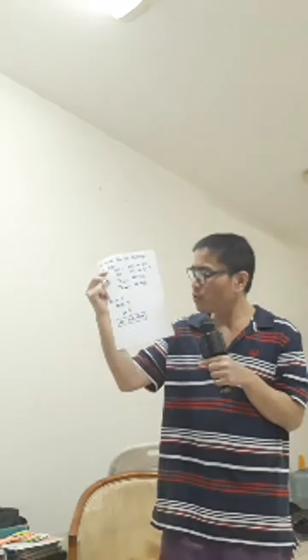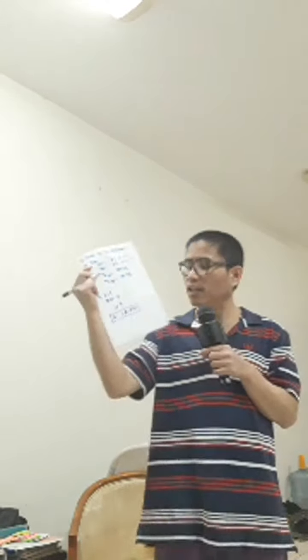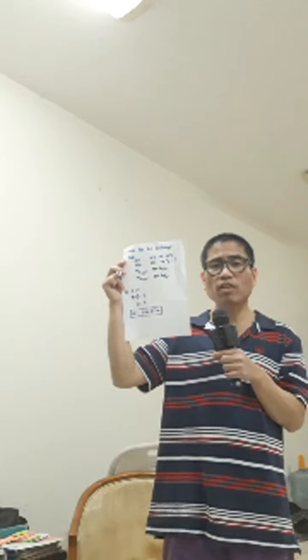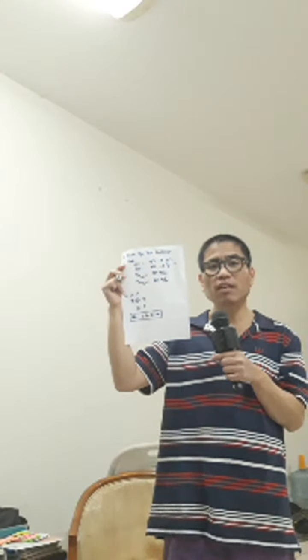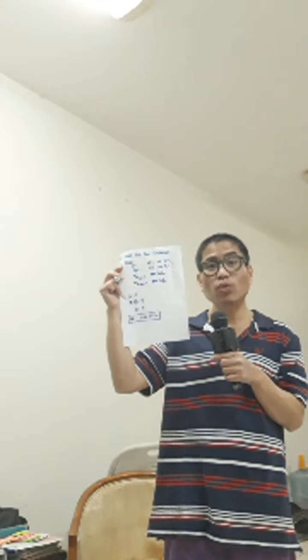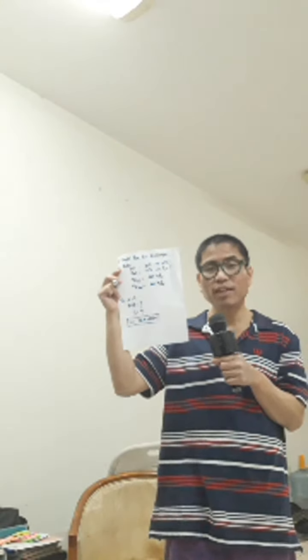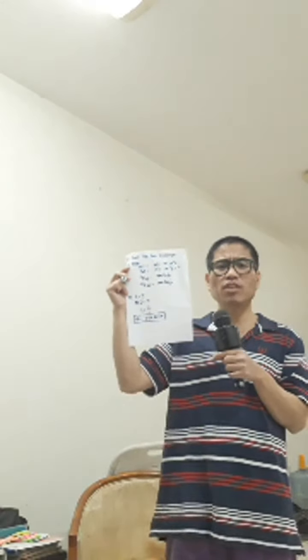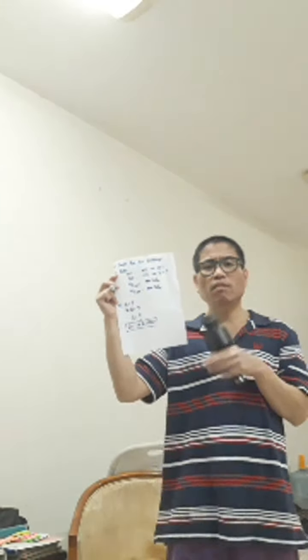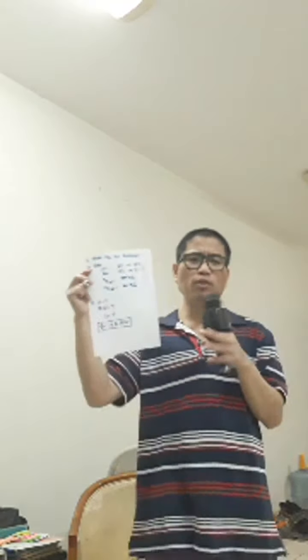Okay, Q is equal to UA delta TLM. Sometimes we also need to put F beside the overall heat transfer coefficient if it undergoes fouling. We need to get the correction factor F, especially if there are many passes somewhere along the way in your heat exchanger. It will pass to another stage, blah blah blah, especially the shell and tube heat exchanger.